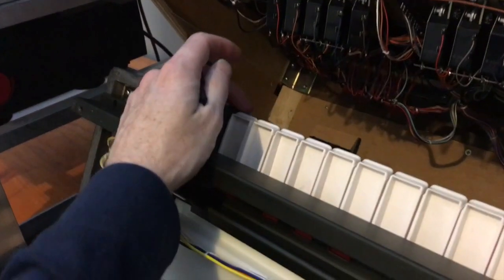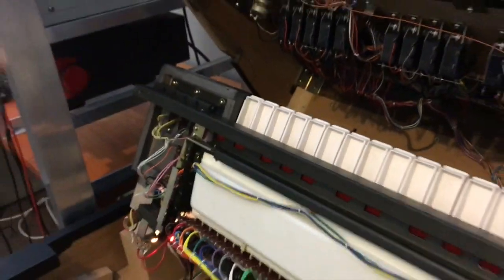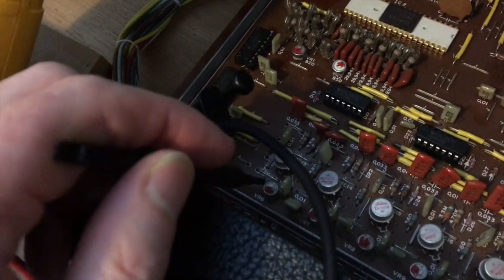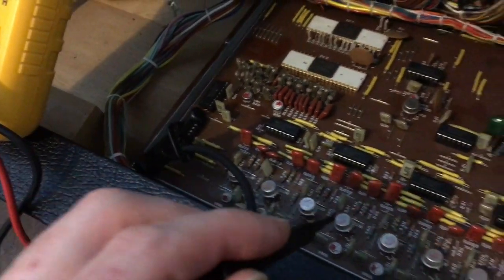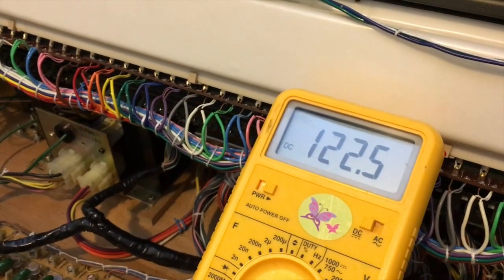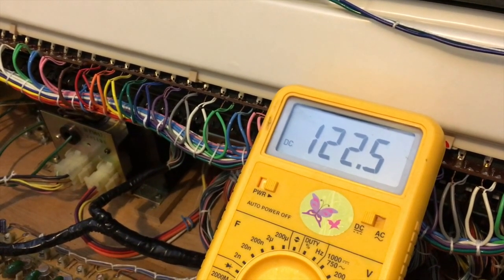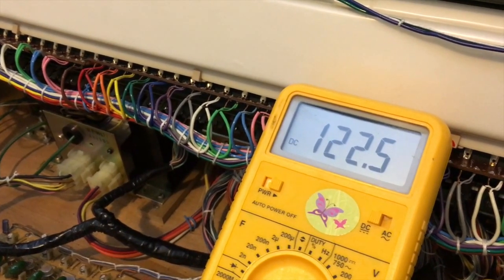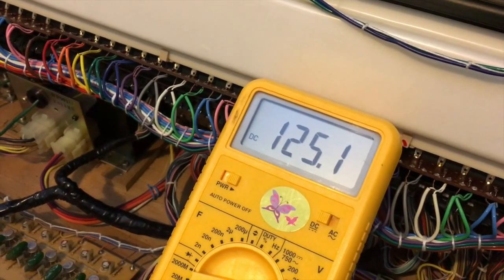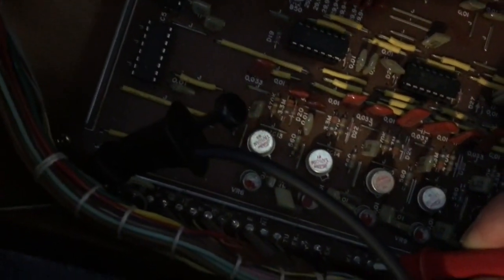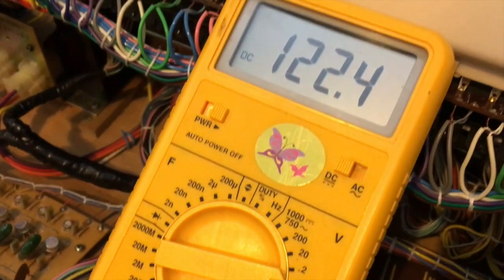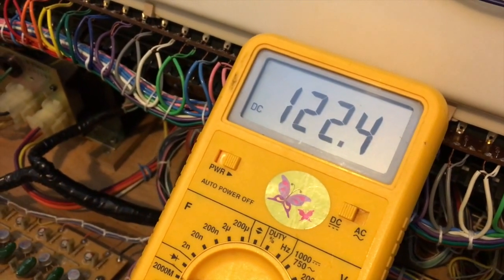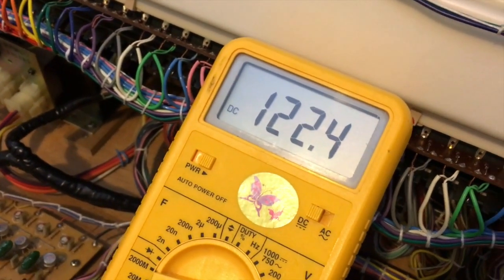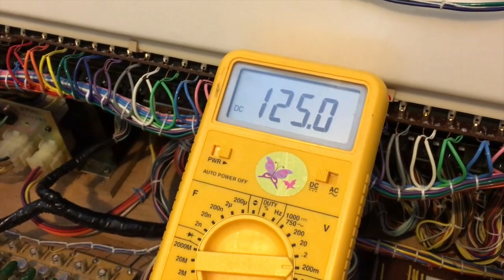So what we do is first we press down C1. So we're looking for that 125 millivolts again. And we use this VR6 for K1, and then we keep going down like that. Okay, so K1 is a little low, so we need to get that to 125, so I'll adjust VR6. Okay, so that's K1 done. So now look for K2, which is just underneath it. And it's still low, so I'll have to adjust each one up to 125. Right, so all 8 are 125 now. So we're done on the KAS board.